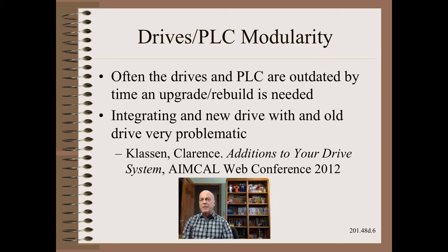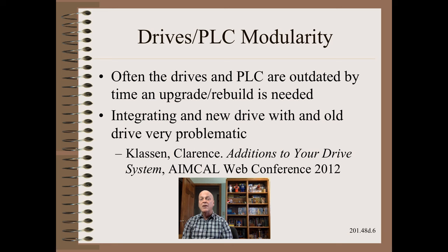Drives and PLCs may not be so much of an issue for two reasons. The first is the service life of these devices is quite short — not much more than 5 to 10 years — so you might just replace all of this during a major upgrade. Second, if we buy more drive rack space and I/O than we need during the original design, then adding more motors and controls may involve only a bit of programming and wiring. This may be well worth considering since integrating new and old drive components is very challenging, as covered by Clarence Klassen in a recent AIM-Cal conference.